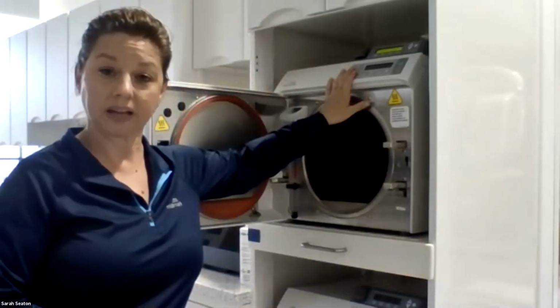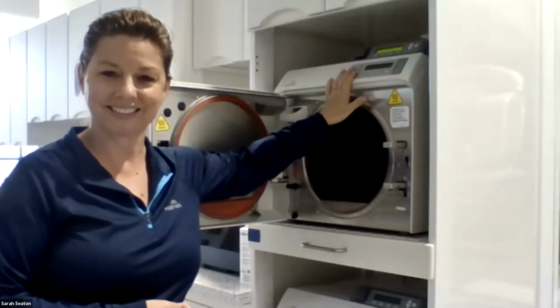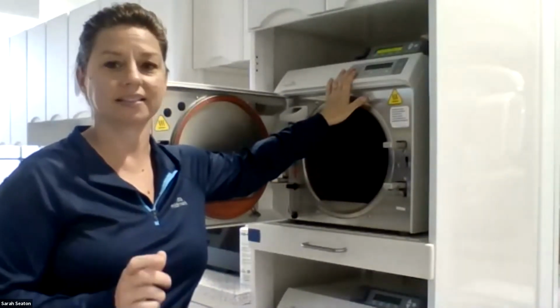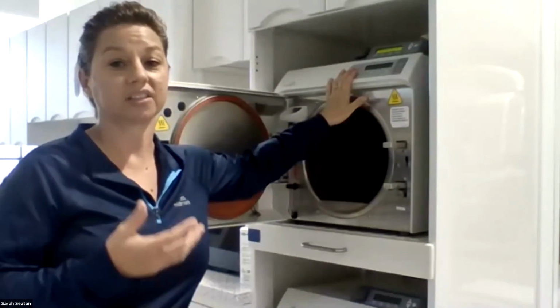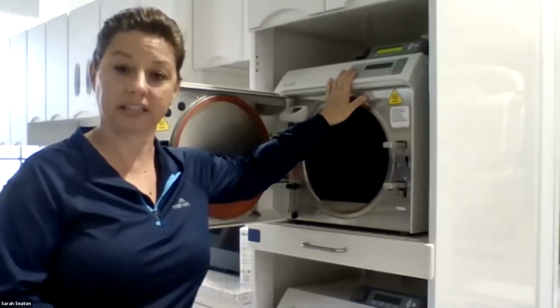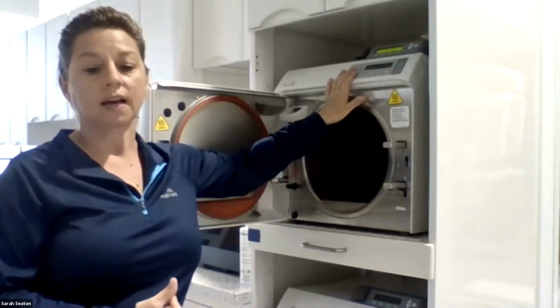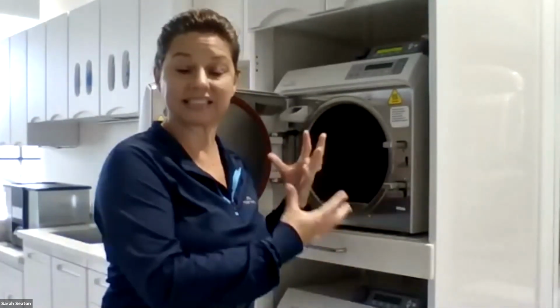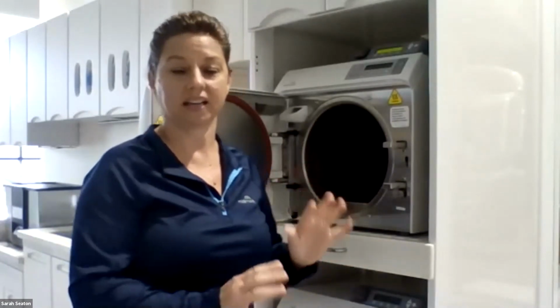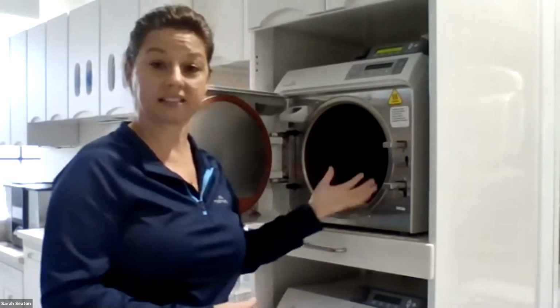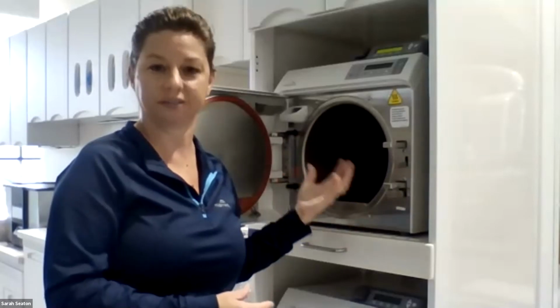So now moving on to the monthly maintenance. As I said, with the weekly maintenance, you're gonna get a reminder on your display every 7, 14, and 21 days. On the 28th day, it reminds you, hey, it's time to do your monthly maintenance. So that's a much more in-depth process of cleaning your sterilizer. It's very important to also note that whenever you're doing any of these maintenance cleaning procedures, you do need to use only speed clean. That is the one product that we have tested with the inside of our working solenoids and valves to know that it won't cause any issues, okay?